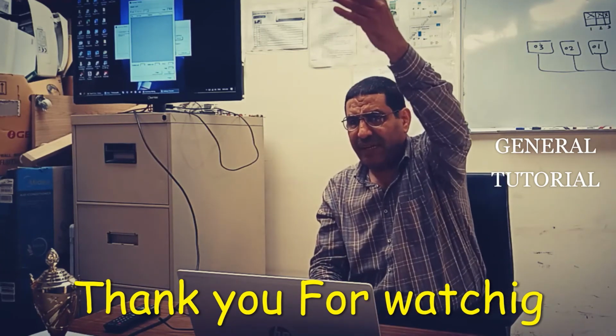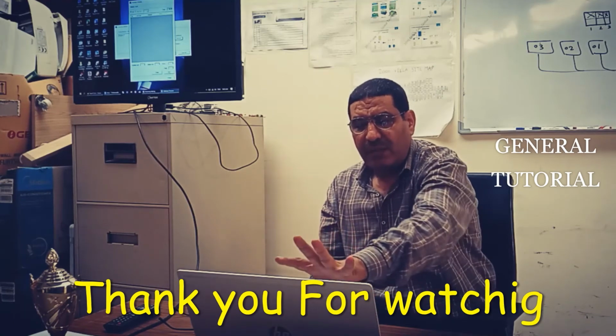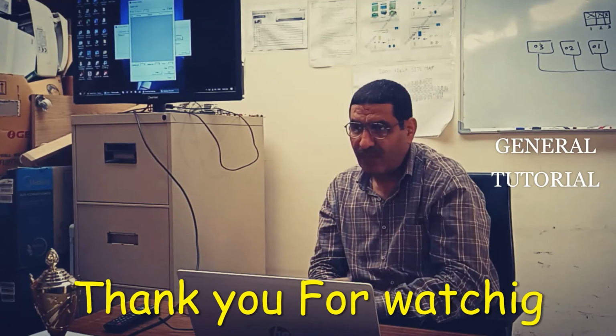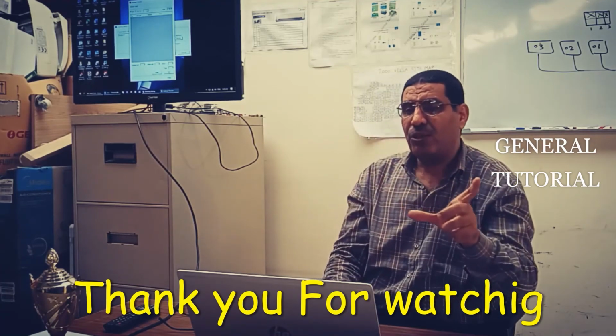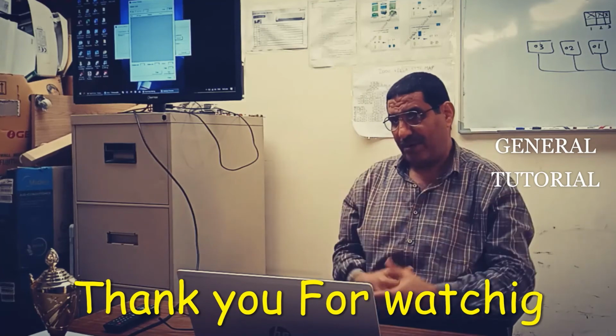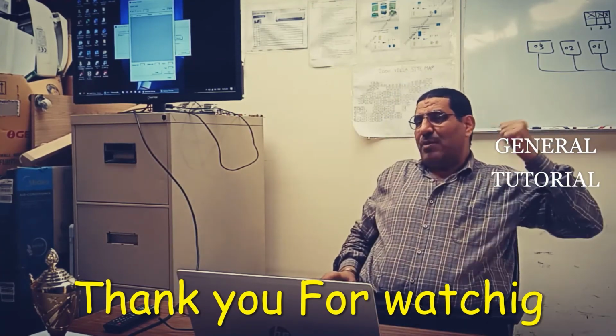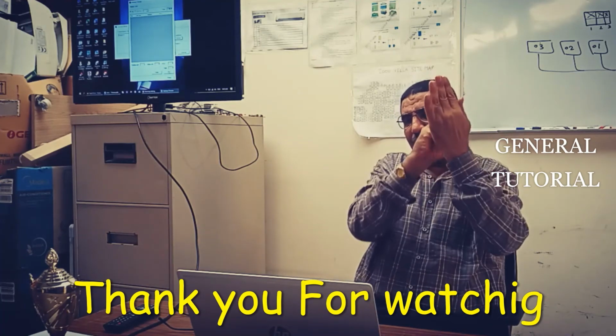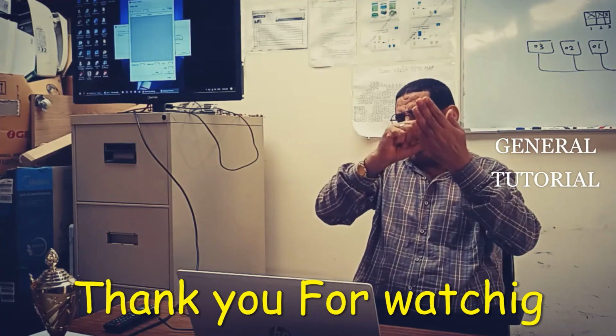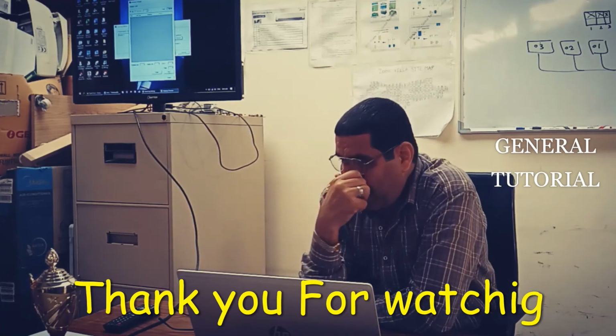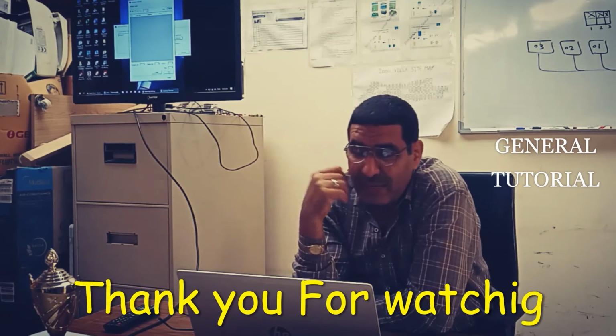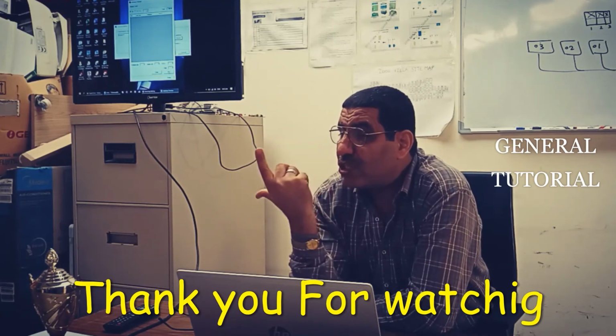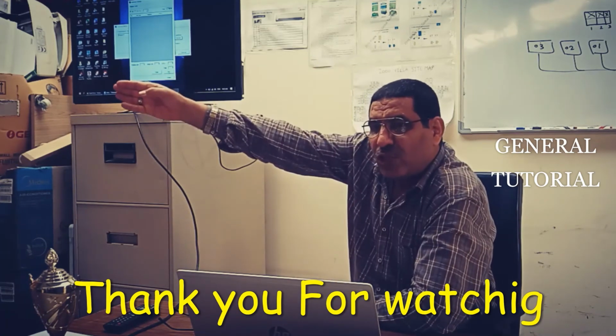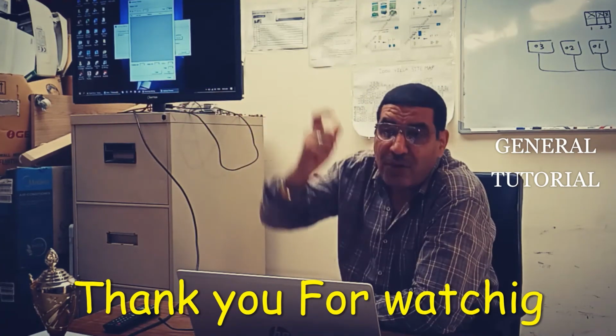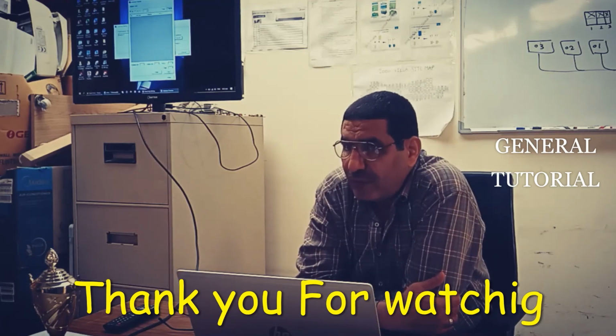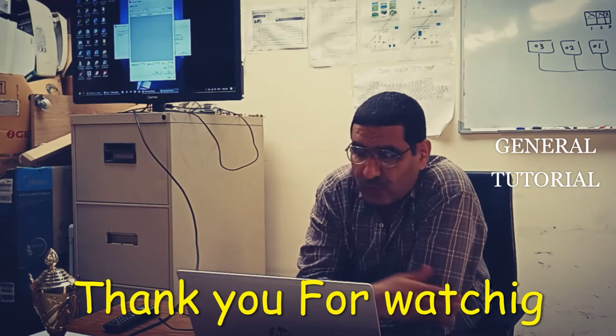And start makes a scan, a check. Okay. Maybe some unit is missing. Right? Maybe two units have the same number. And you remember, when we made addressing, I wrote a paper with the address number, serial number, model number and location. Okay, which unit is missing? I will go there. For example, indoor unit 03. Where is 03? I already have the paper. I go to the room that has 03. I check. Maybe it is switched off. Understand?